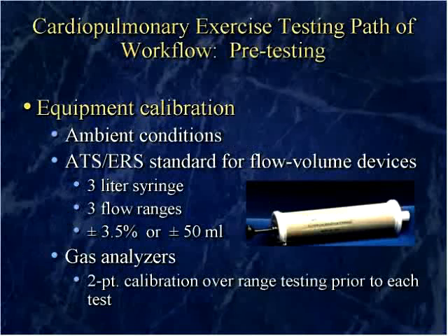As far as pre-test calibration of the system, in our institution we calibrate our system prior to every test. I know that some people will calibrate their flow sensors at the beginning of the day maybe, and then their analyzers just before the test. But certainly we need to make sure that they are calibrated and meet the ATS-ERS standards for flow volume measuring devices.